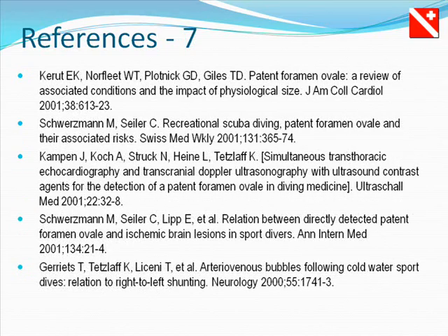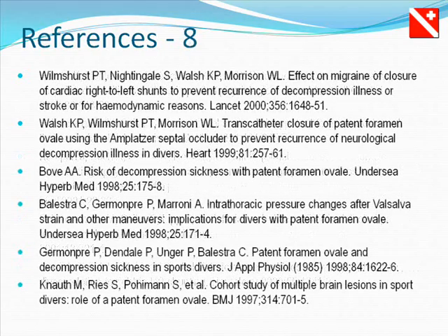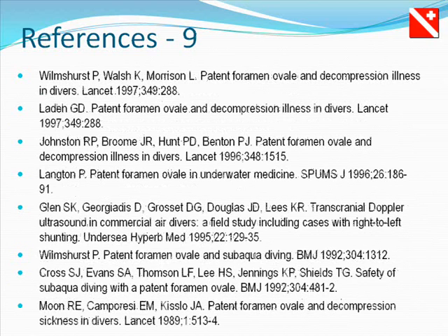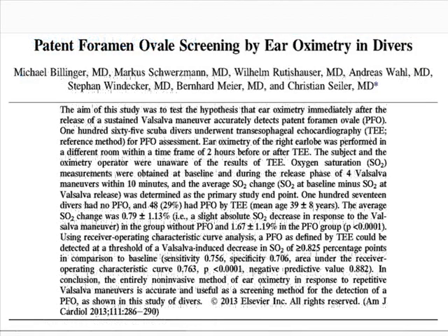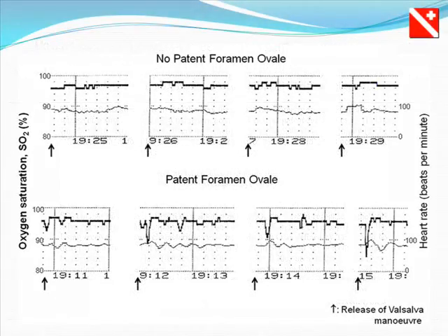After first reading of this article, which I received from you, thank you very much, Frans, for this. But they reported they are using a Nellcor pulse oximeter. The problem is that they are showing only the first 2 digits. They are not showing the decimal place. And so technically, it is impossible to receive the 0.825 percent point as a decrease.